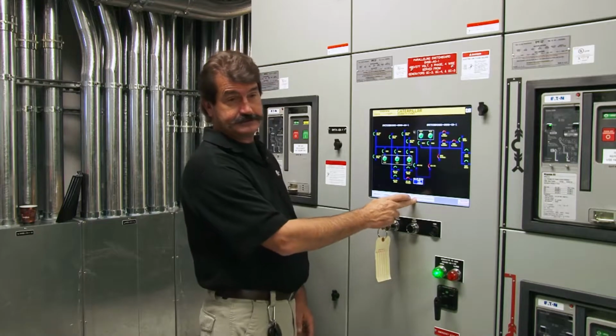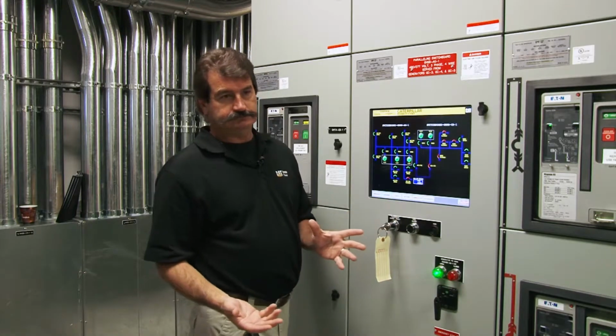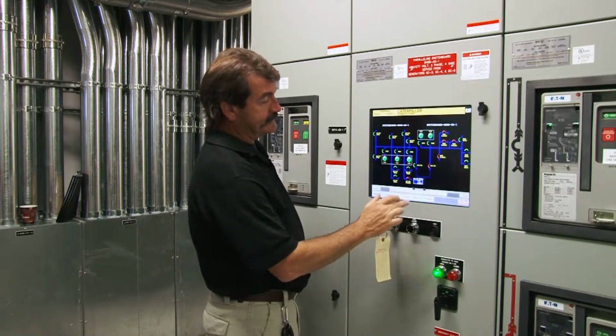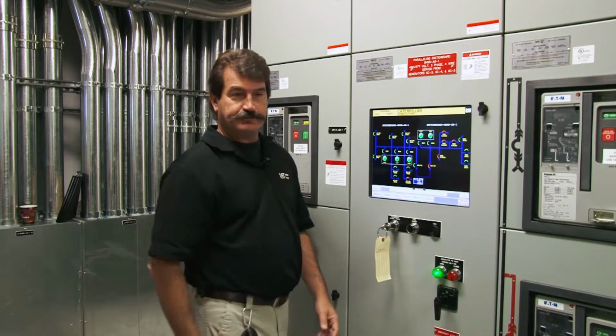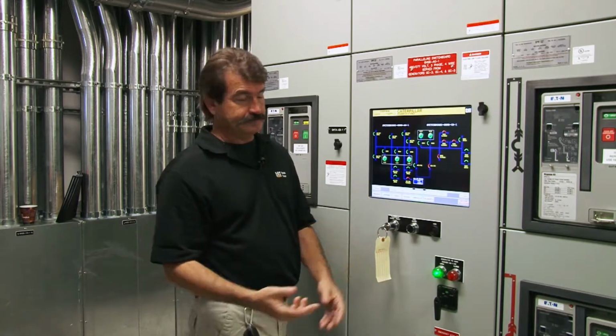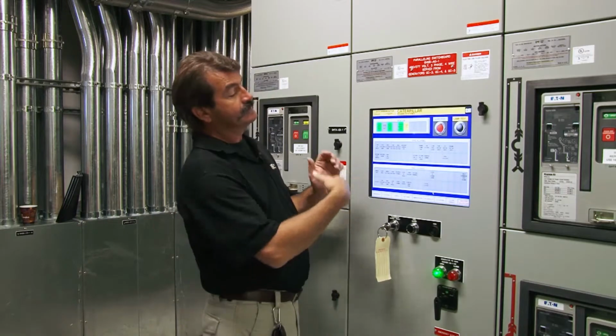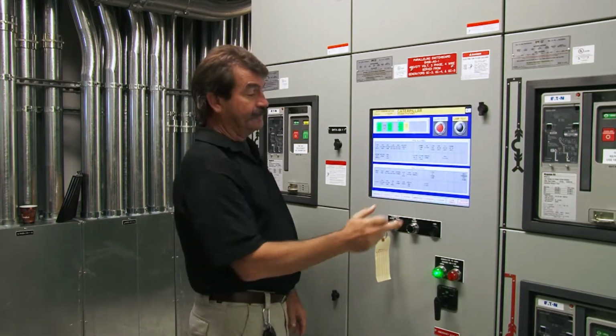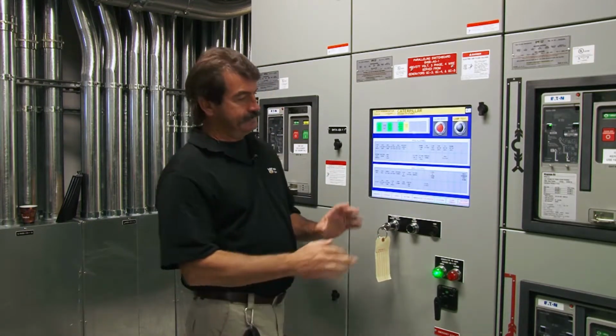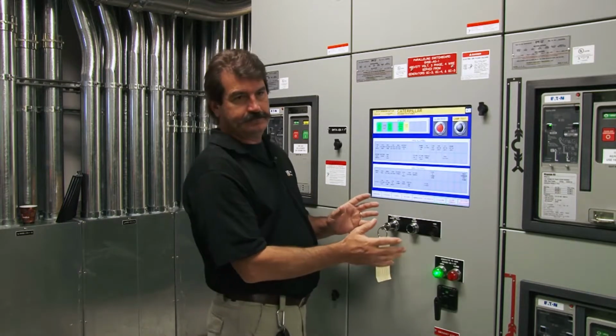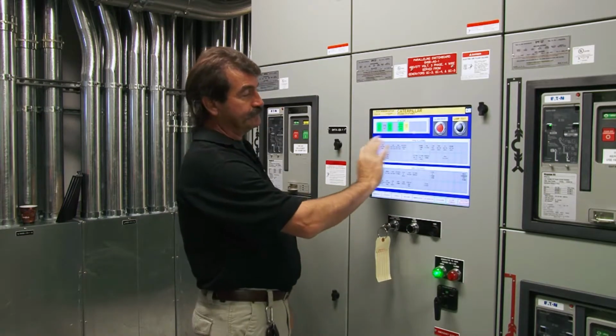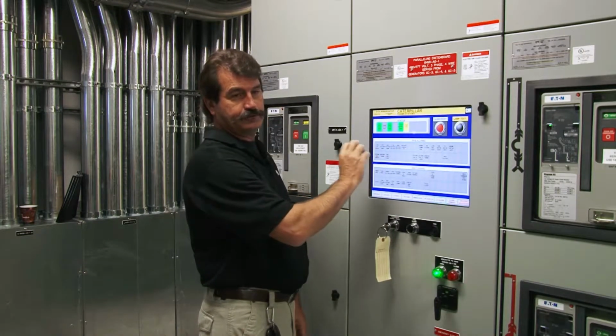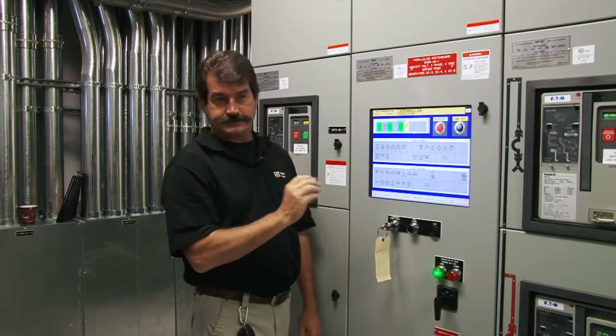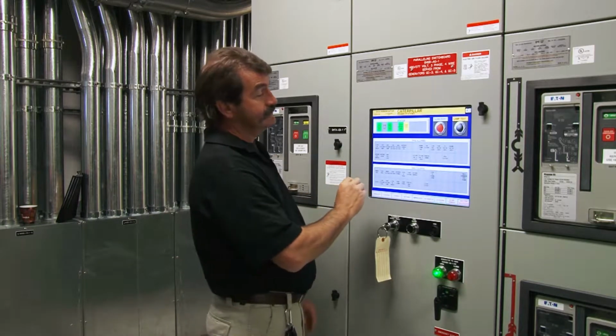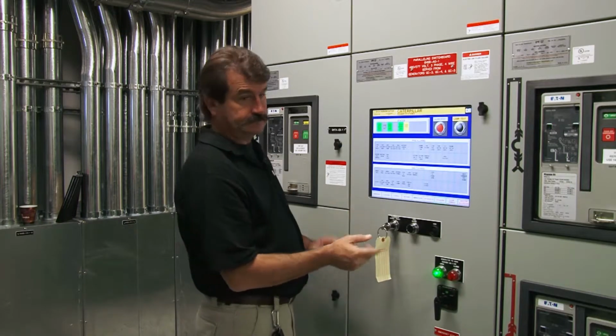Anytime this thing blinks, you've got a problem. You'll see it blinking, pull it up, whichever one is blinking, that's where your problem is. You navigate to there, look at it, hit alarm acknowledge. I have to hold it for just a little bit, and then whatever problem you had will go solid instead of blinking, and then you can see what's going on.